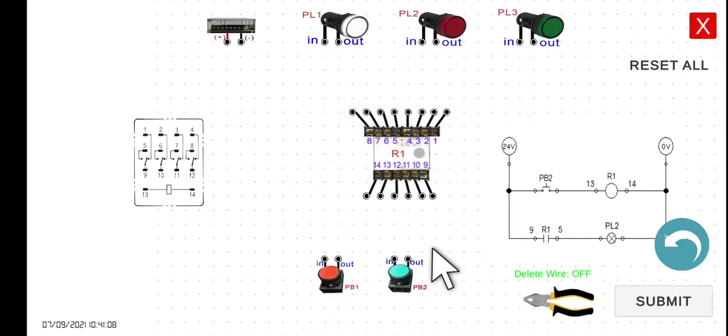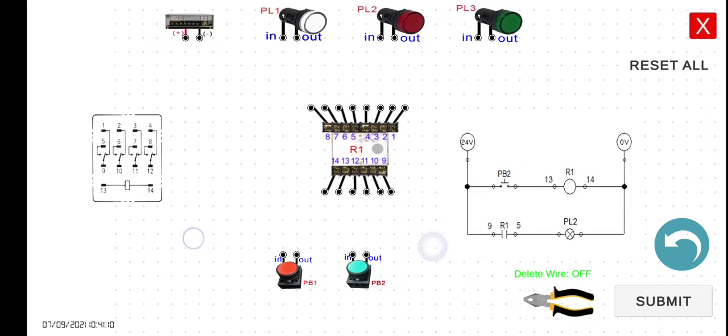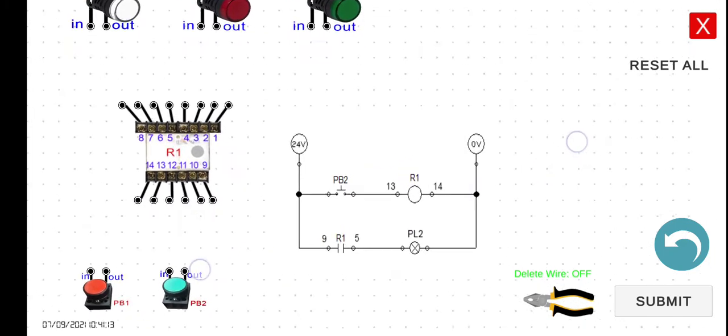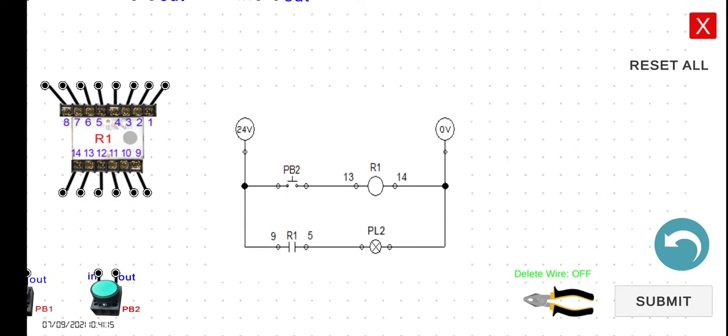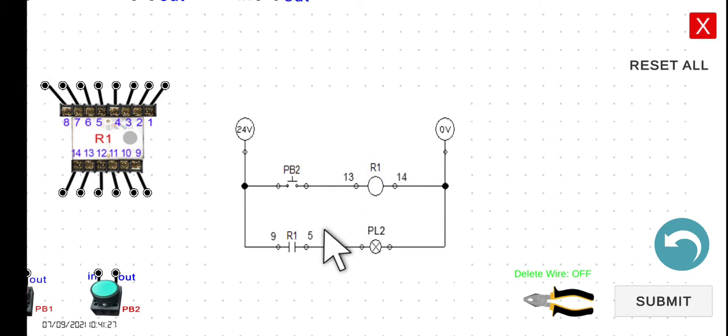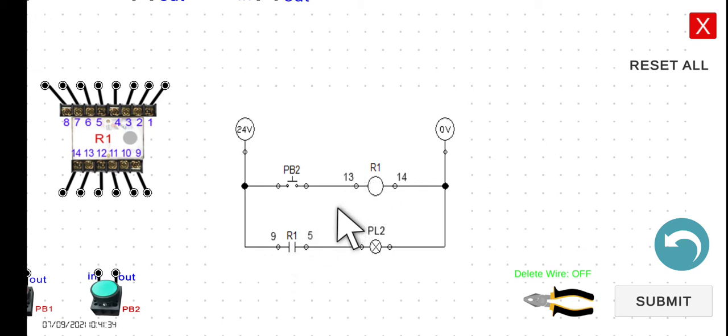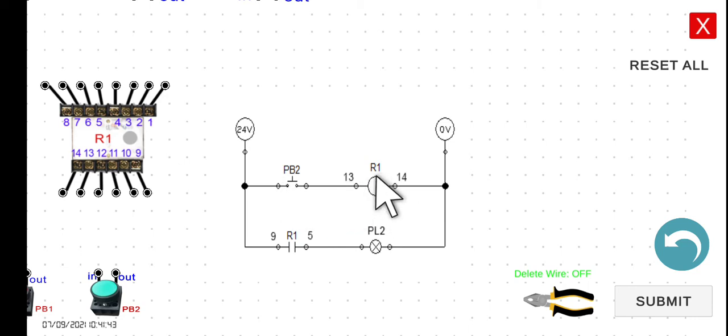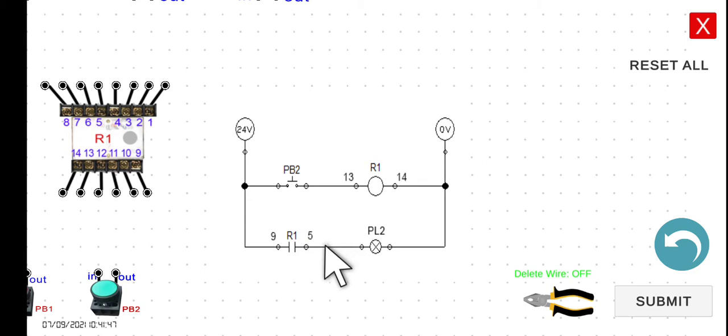Let's analyze first the functionality of our circuit. As we can see here, we have a normally open push button and then we have the relay of the coil, the same with the magnetic contactor. It is very important to take note of the label of each component here. We have R1 here and then we have R1 for this particular normally open switch. This indicates that this R1 here and R1 here belongs to a single component, which is in this particular case, the relay number one. It means that same with magnetic contactor, if this coil is energized or there is a current flowing through this coil, this R1, which is normally open, will be closed.